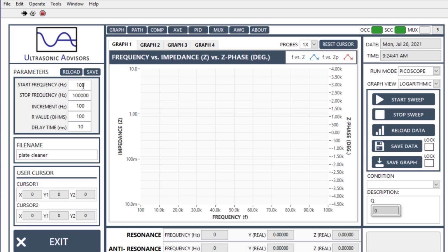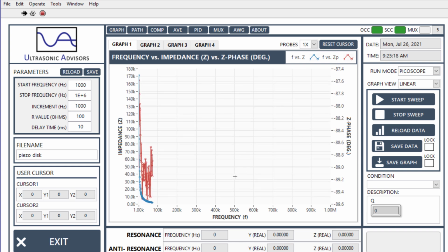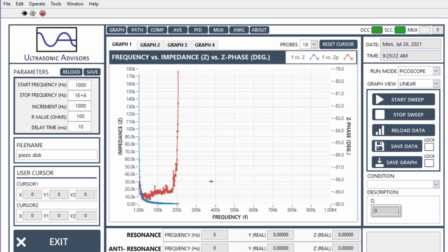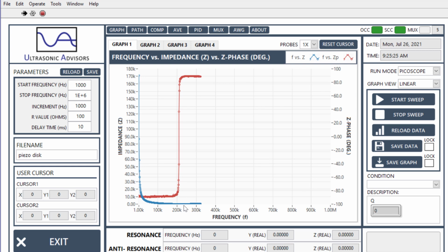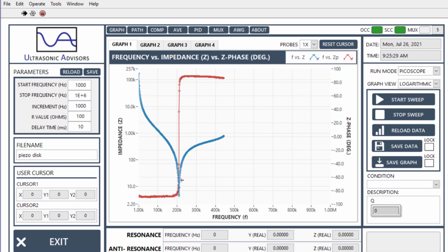So let's go ahead and run our test from 1 kilohertz to, let's do 1 megahertz. Frequency steps of 1,000. And now we're measuring the piezo disc. And we'll load the regular settings of impedance and phase. It's the easiest to kind of visually interpret what's happening, although for specifics you'll need to go for real admittance and real impedance. So the phase is about -88, and here we have a resonance occurring.